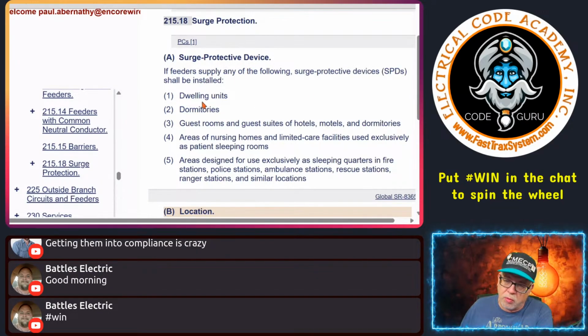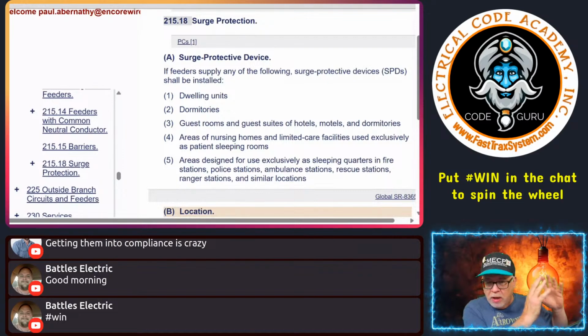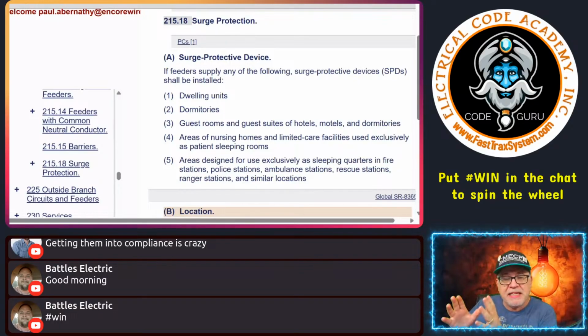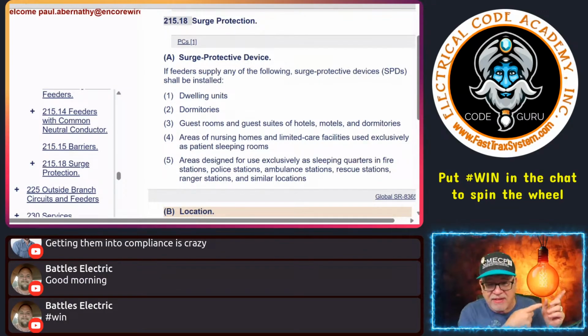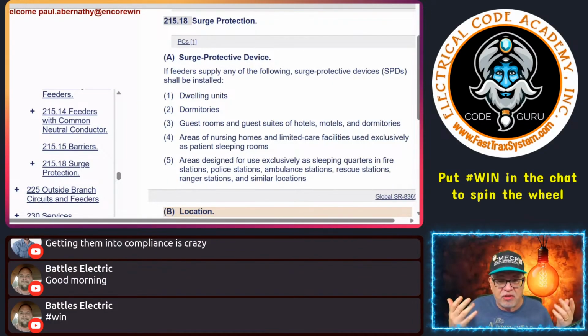So the reason they tried to get this one changed was to add extra language so that it only applied to the multifamily dwelling. But then people argued that's not going to work, because that means you may not have an SPD at the actual dwelling unit. If the panel is remote, let's say a service is on a pole 30 feet away from the house because that's what the owners want, and now a feeder's coming, they don't have the SPD at the actual dwelling unit. And adding that language is going to cause confusion. My point was you already have it at the service, even though it's maybe remote, the homeowner needs to know where to go to check it. Also, there is an allowance to put it on the feeder. So that's really a design decision between the installer and the owners. That was my opinion, but the code panel group all disagreed, and this is probably what's going to go in right here.